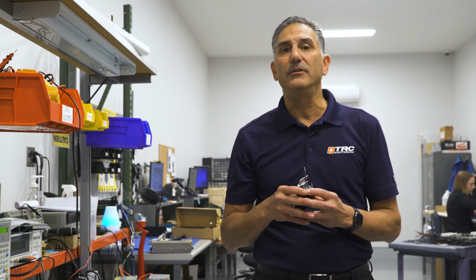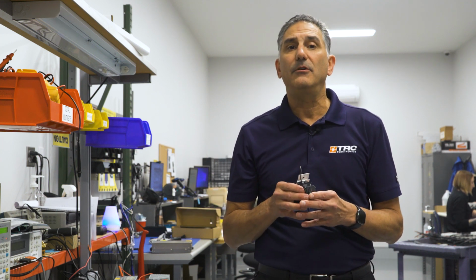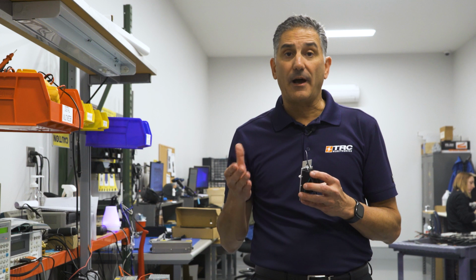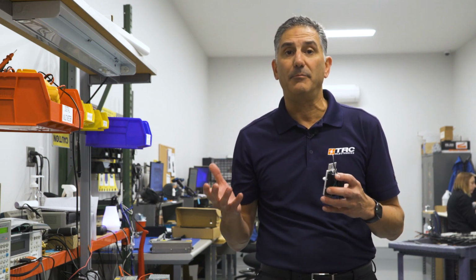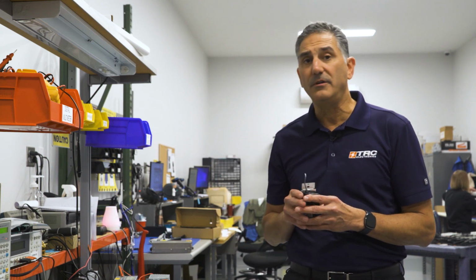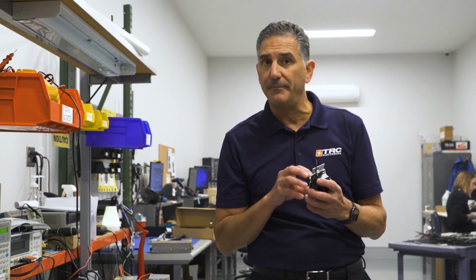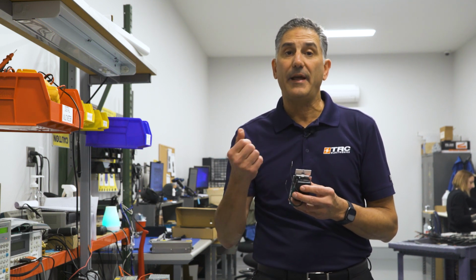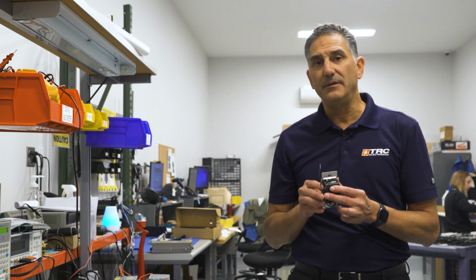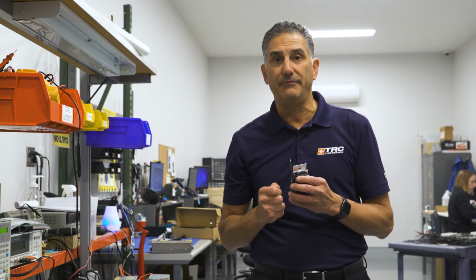Now, all of these drivers are connected on the secondary side, or the DC side as we call it, because they are low voltage and they operate at a safe voltage, and also they can be controlled by other types of computerized dimming systems for inside building infrastructure. Now, it's important to note though that when you're selecting the dimmer, or the dimming system, you know exactly how much current this dimmer can handle, because the way these dimming systems work is they're actually going to pull current from each individual driver.